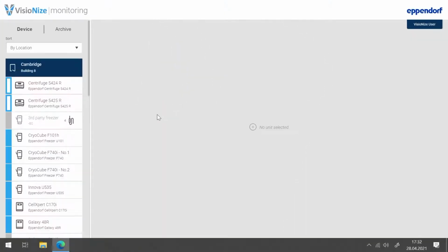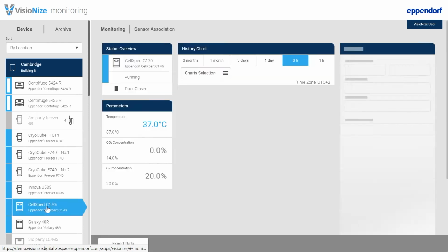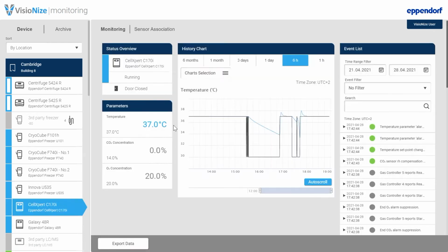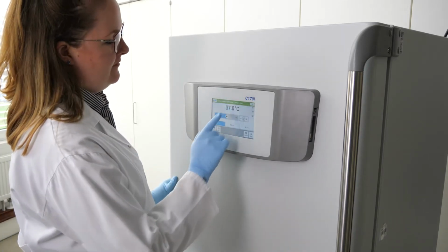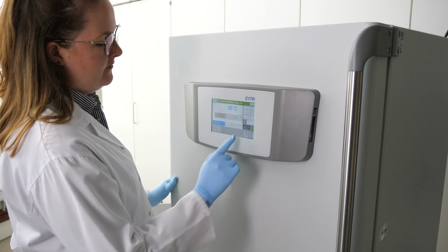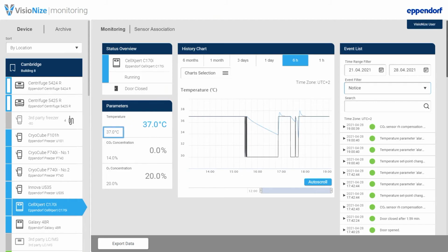Using the monitoring application, you can remotely monitor your devices. So let's have a look at the C170i. You can monitor all parameters like the temperature, CO2, O2. All historical parameter data is saved in a chart view, and all device interactions are saved in an event list. So let's change the temperature from 37 to 30 degrees. The set point change is displayed in the monitoring, and also the set point changes are documented in the event list.